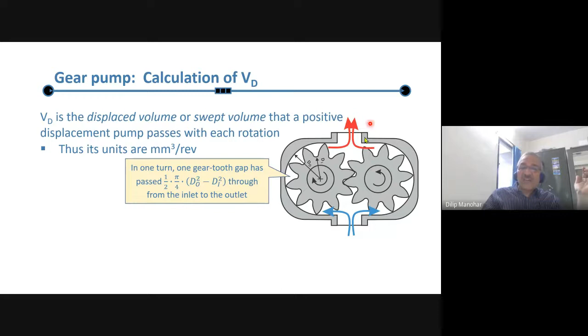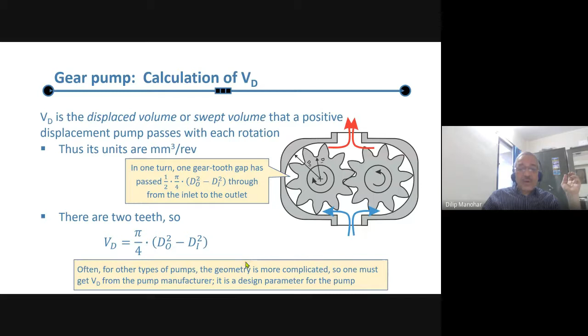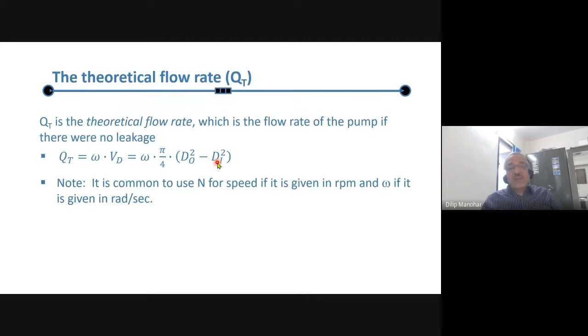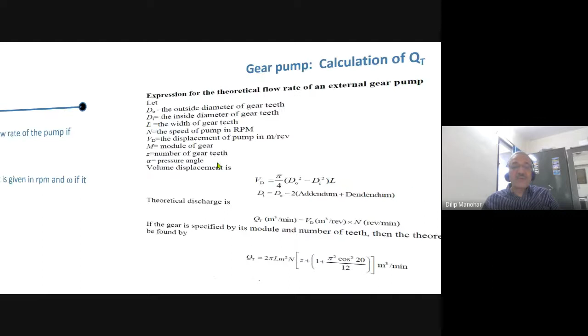So for one gear it is this. For the second gear it will be similar. If there are two gears, the volume displaced for one revolution will be pi by 4 into DO square minus DI square. We can convert that into the theoretical flow using this formula. Theoretical flow is omega, the angular rotation, into the volume displaced per rotation, so pi by 4 into DO square minus DI square. It is common to use N for RPM instead of omega. So we convert that into a formula.